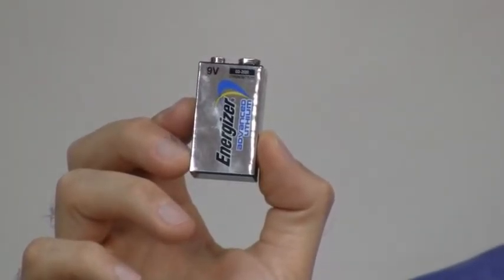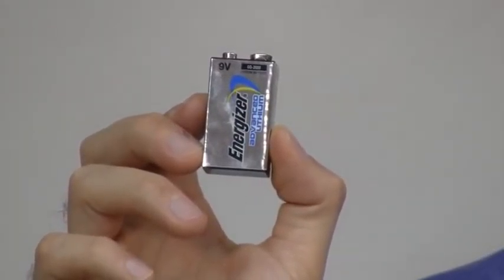The battery is rated for a 10-year shelf life under normal circumstances. The battery allows the AC Pro to be commissioned and for you to review last trip data when there is no CT power. The AC Pro is normally powered by the CTs. The battery only powers the unit when there is less than 10% current going through the CTs. If the battery dies, the AC Pro will retain all of its protective functions and settings. The last trip data will also be saved.